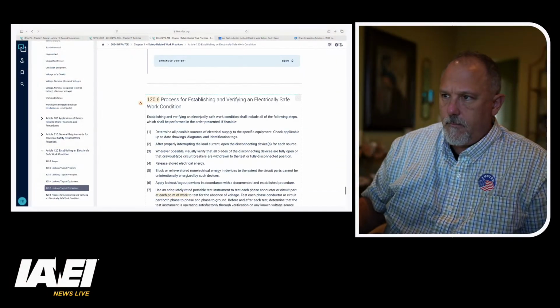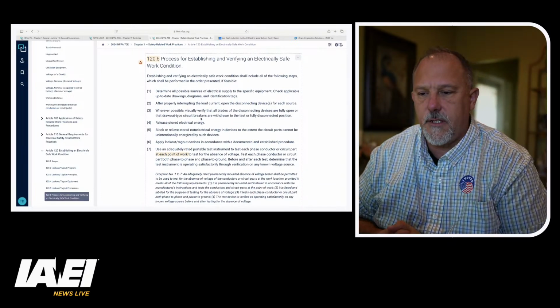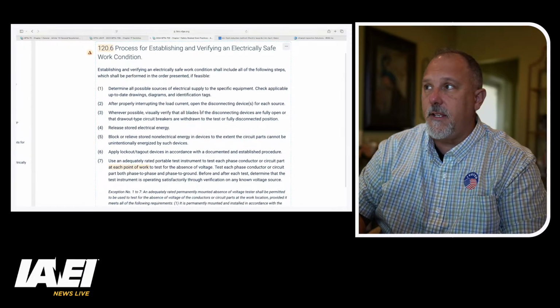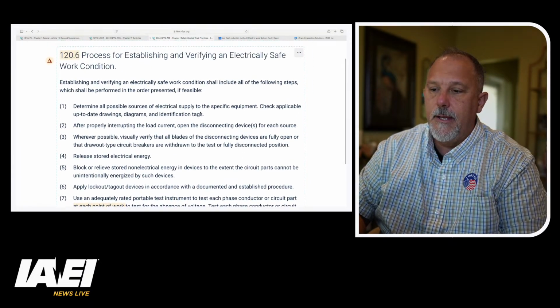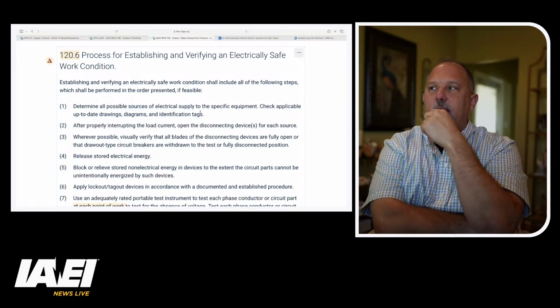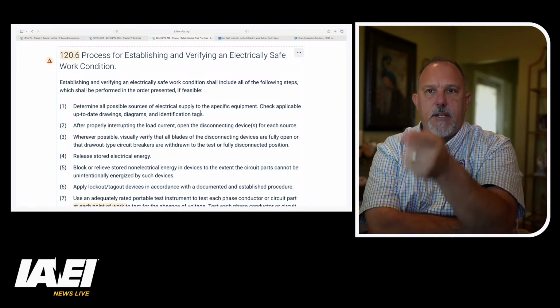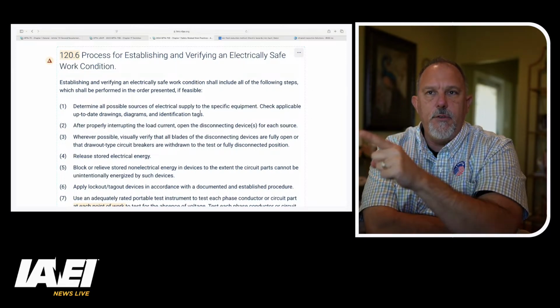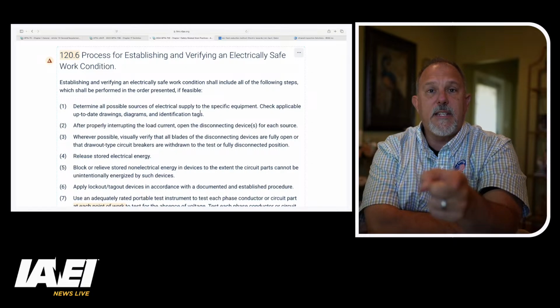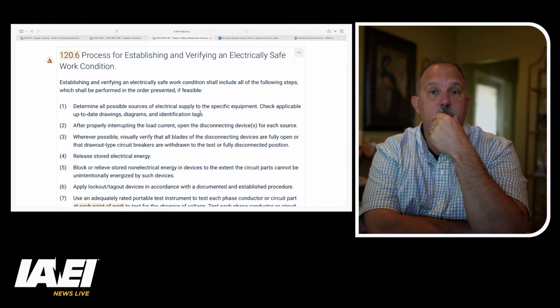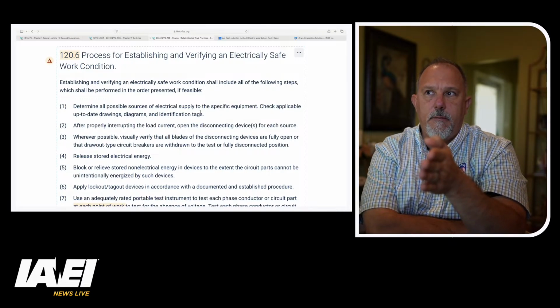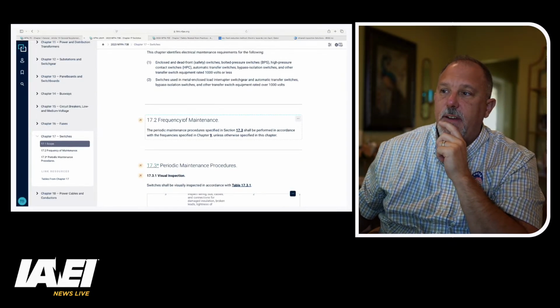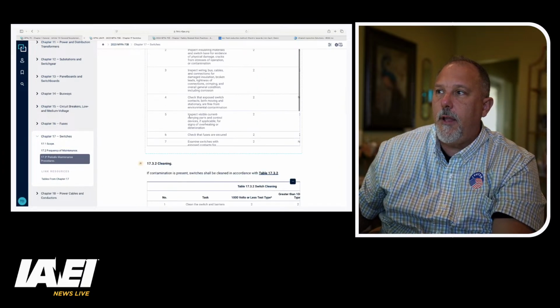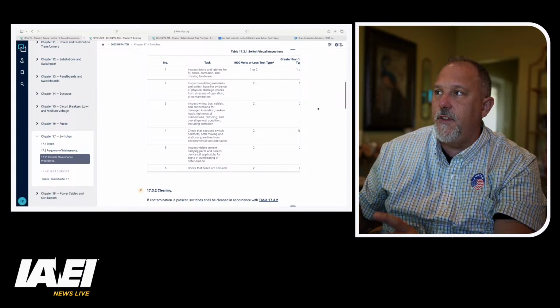I could do that. My only concern is, so here's what I'm doing. I'm in 70E, and I was looking at the process for establishing and verifying an electrically safe work condition. I'm using NFPA Link, so don't forget to get your copy of NFPA Link. So my thought process is, let's take that non-fused disconnect switch, and let's say it's got infrared windows on it. I know I have to do thermography. And if I go to 70B, it tells me that I have to do visual inspections.